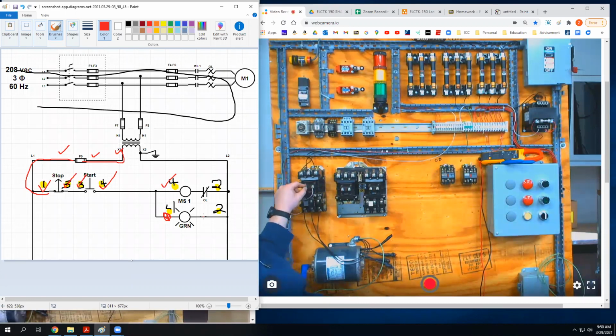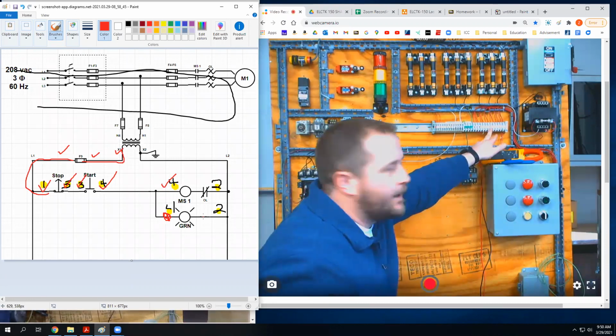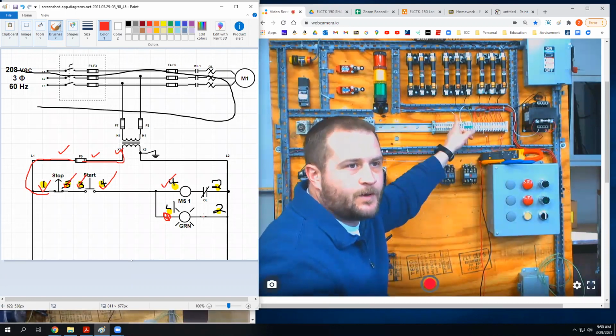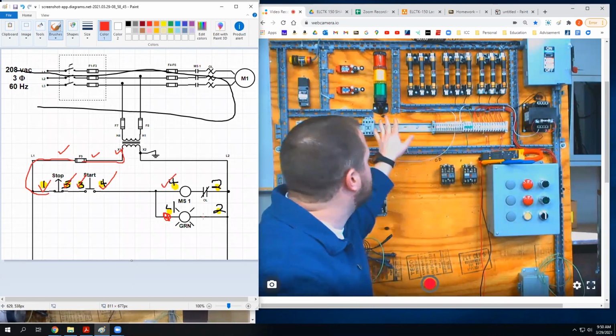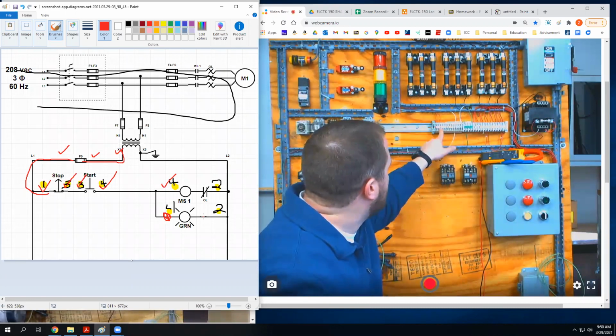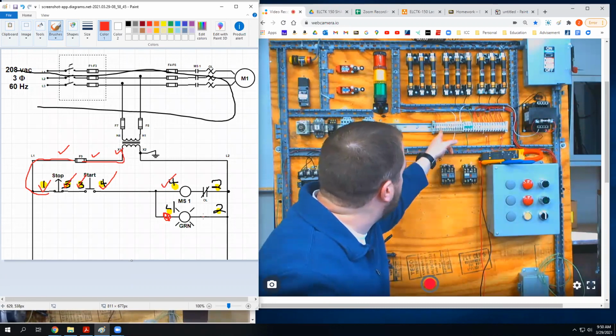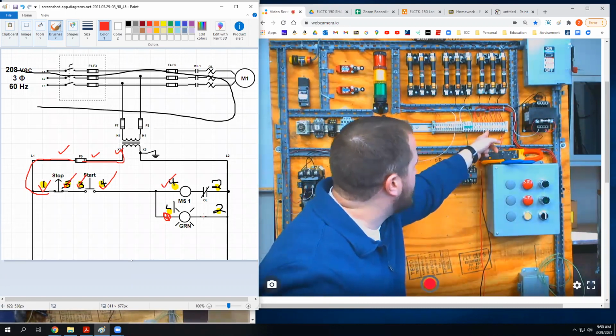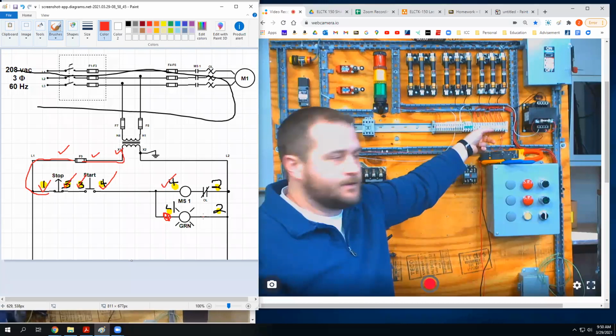If you can avoid putting 5 wires under one terminal, pull from a different place. But the thing in this scenario that makes the most sense is run a number 4 wire from here over to here, because this is where my closest number 4 is. Make sense?